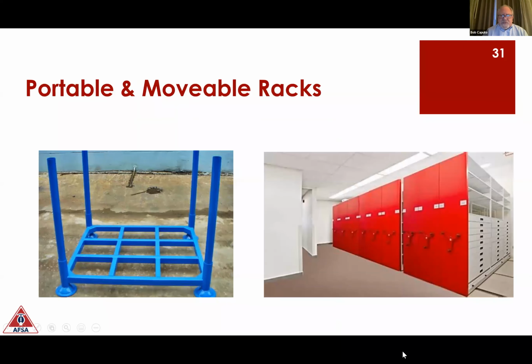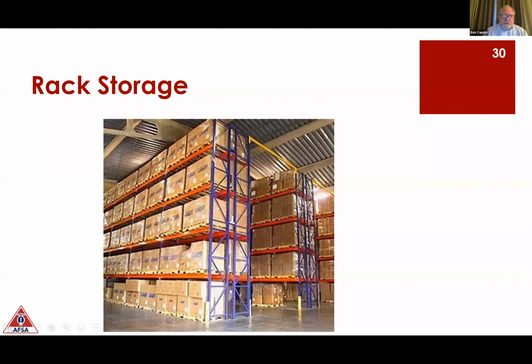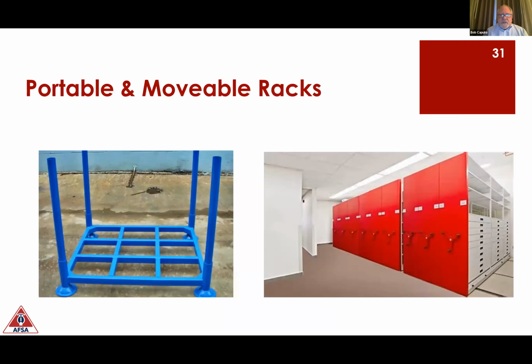Now, depending on the sprinkler system that they have in the building, there's a certain amount of clearance required at the top of storage to the sprinkler, so that the sprinkler, when it discharges water, can develop a pattern, and that pattern of water spray is not restricted because the storage is too close. We also have the other challenge where the clearance above storage is too big, and the fire's growth or the heat cone can be much larger. So we have both issues. That's why we need to know what's the storage height and what's the ceiling height.